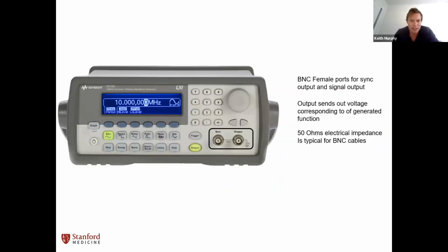Okay. So another thing, Kim. What is that burst button for? It's interesting because in ultrasound imaging, burst just means a long pulse. And sometimes people use it to mean other things when we're trying to move away from that. What does it mean here in this context? It does actually mean, and maybe we'll come to a standstill on this, but on this machine, a burst is literally to run a certain number of cycles at a certain frequency, and then to define the interpulse interval. So I think it actually just means exactly what you're describing.